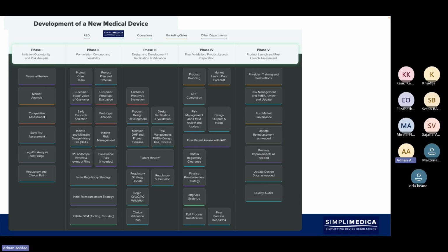And then we look at phase two, when we're looking at conceptualizing the idea, feasibility, prototype analysis, some early risk management, some preclinical trials, and then we move into phase three, when we really get into the weeds of verification and validation testing. And then we look at stress testing the device and the prototype before we look at final validation. At this point, we're really looking at finalizing the medical device technical dossier to make sure that we've got all the evidence that we need to make sure that the device has completed all of the regulatory requirements and is ready for submission.